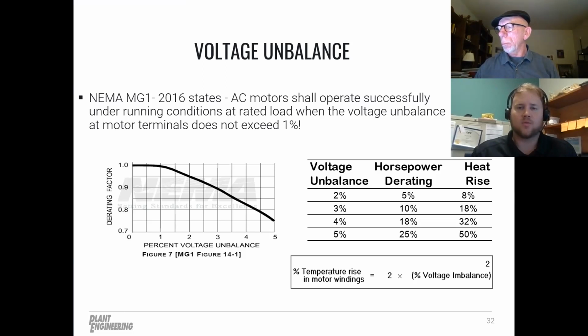Of course, voltage imbalance isn't the only cause of current unbalance. Unbalanced winding resistance could lead to that. If you are measuring the current unbalance with an ampere meter, whether your motor is loaded or unloaded, that's where you can go back to the maintenance technique we talked about earlier. De-energize the motor, measure each phase-to-phase winding resistance, and verify what your baseline unbalance may be.